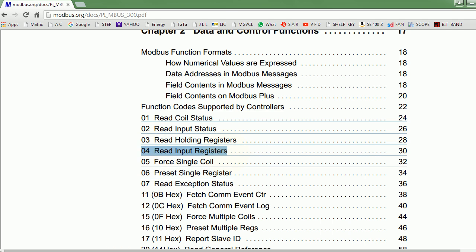Input register values would typically come from some 4 to 20 milliamp input device. As I showed in the first video of my setup, I have an analog input module which is a 4 to 20 module. It is interfaced with an RTD - specifically a PT-100 sensor - through a PT-100 to 4-20 converter. The converter sends analog inputs of 4 to 20 milliamps to the PLC, and that's how the PLC knows the temperature at that PT-100 at that moment. So you can't really set analog input values - the external device in our setup does that.